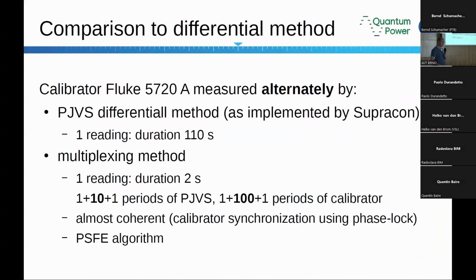In the multiplexing method, I have just switched between the voltage of the calibrator and the Josephson, and voltage of the calibrator and Josephson, repeated many times. For the actual Josephson part, I have sampled 12 periods. In effect, I have used only 10, and the first and last period of the Josephson were thrown out because the multiplexer settles down. So I have cut out this data. And for the calibrator, I have sampled 100 periods, and again, one before and one after were thrown out.